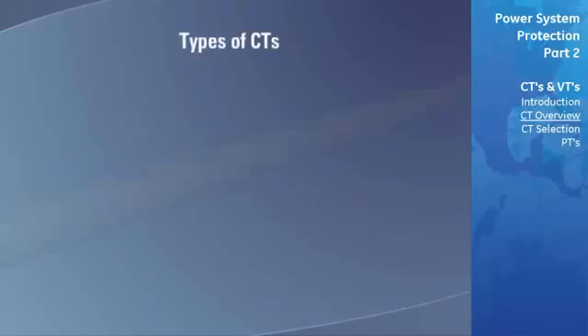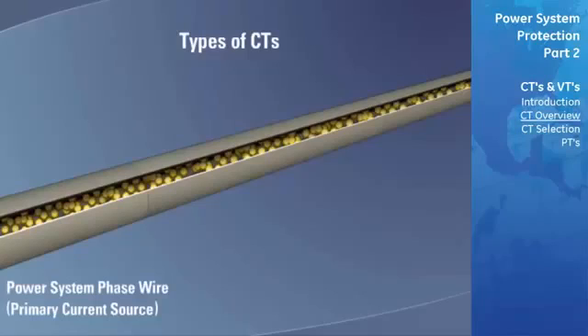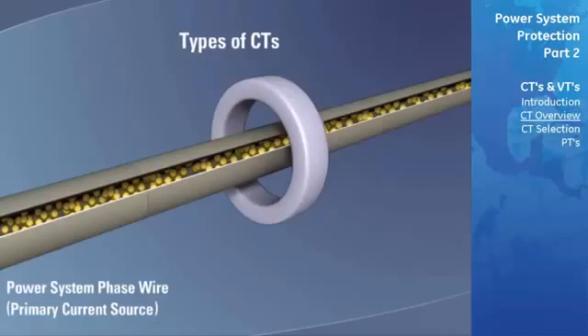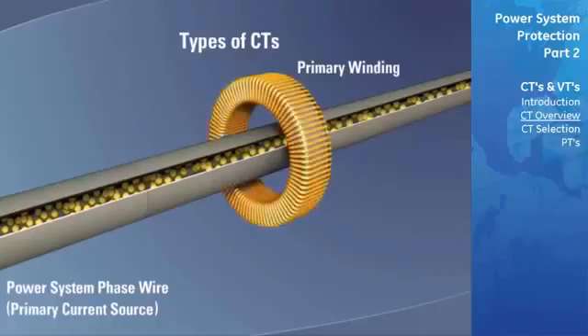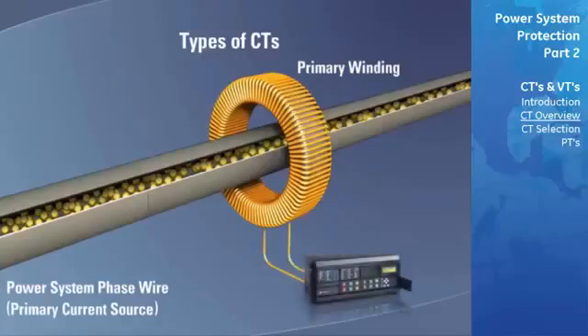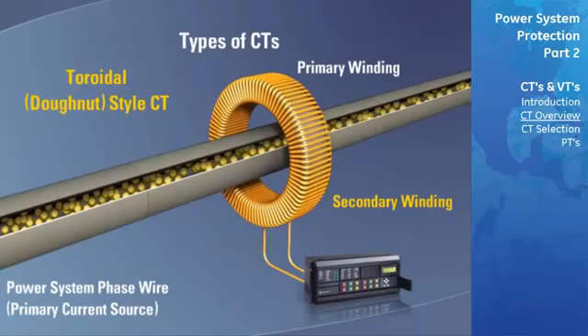A common current transformer construction is one in which the power system phase wire is passed through the hole in the center of an annular core or ring, which is called a window. This forms the primary winding. A second insulated wire is then wound around the core and then brought to the relay for measurement. This is known as the secondary winding. A CT with this type of construction is typically referred to as a toroidal, or donut-style CT.